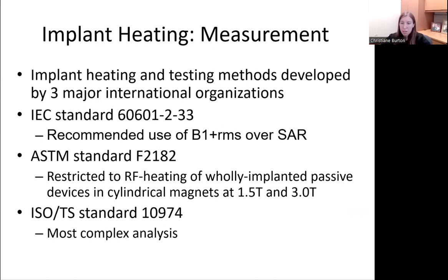Several international safety organizations and government agencies have published relevant standards and methods for estimating and measuring implant-related heating in the MR environment. The three most important are the International Electrotechnical Commission, IEC, the American Association of Testing and Materials International, ASTM, and the International Standards Organization, ISO. The IEC 60601-2-33 is a 100+ page document dealing with multiple aspects of MRI safety and performance, of which implant heating is only a small part. One of the important advances of this standard with regards to implants is the recommended use of B1 plus RMS over SAR, which we will go into in a later slide.